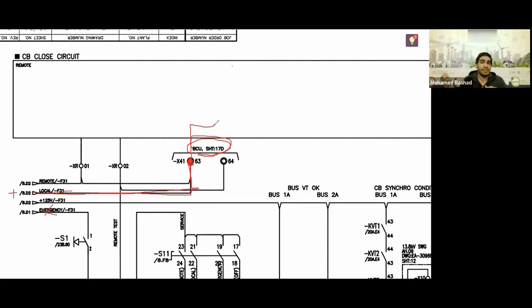Whether you're working with Siemens 6MD, for example, or with ABB REC 670, or even with the MiCOM P264, any of them, the important thing is that initially in SEL 451, for example, you have some logic diagrams inside that you can create. This logic diagram is graphical, or you can write it as commands. But of course, most of it is graphical, or all of it is graphical within the allowed SEL graphical limits by writing it in the form of an equation.